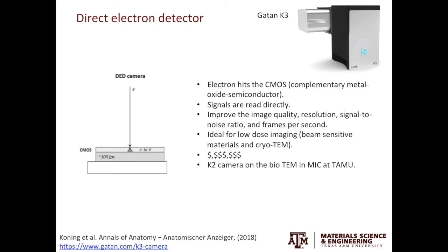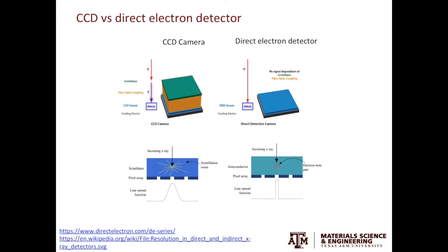The downside of direct electron detectors is that they are very, very expensive. In MIC at Texas A&M University, we have one K2 camera, which is a direct electron detector. To compare CCD and direct electron detectors: signal generation in CCD is a multiple-step process, while in the direct electron detector it's a single-step process. In the CCD camera, because multiple photons are generated and can scatter, you get a degradation in resolution, while in the direct electron detector you don't get such an artifact.